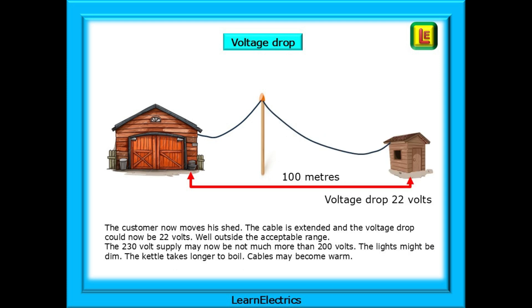The DIY chap now moves his shed a further 50 metres away. The electrical cable is extended, and the voltage drop increases and could now be 22 volts, well outside the acceptable range. The 230 volts supply may now be not much more than 200 volts. The lights might be dim, the kettle takes longer to boil, and cables may become warm. What he's done is added more cable, which is more resistant, which means more voltage drop across the cables.